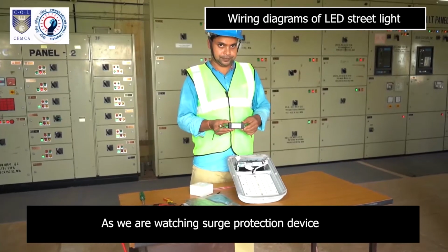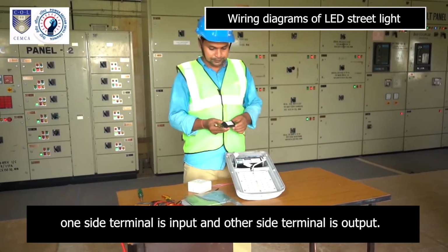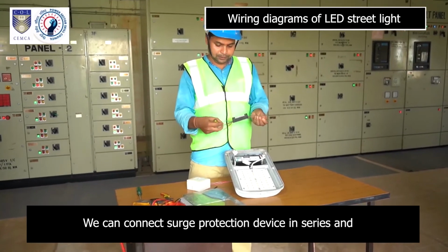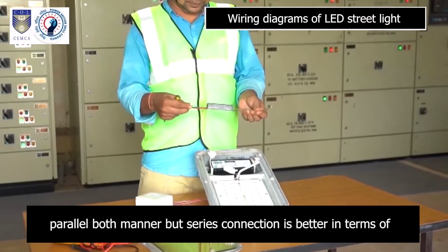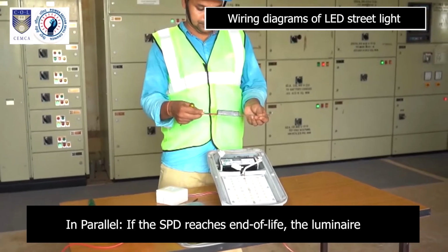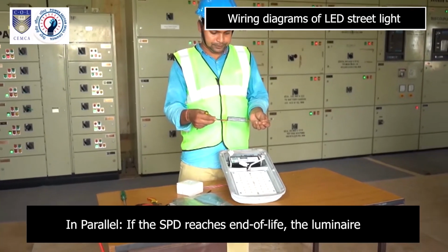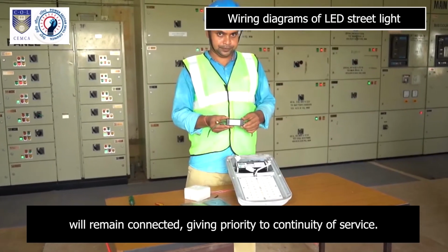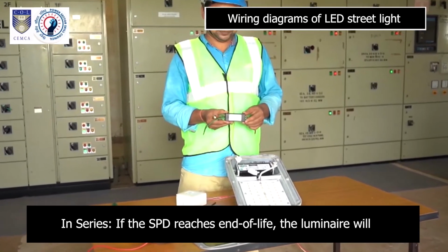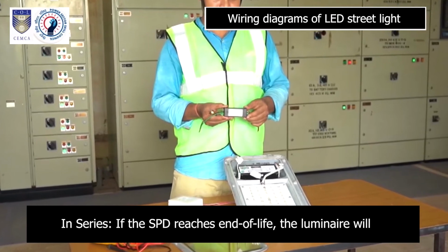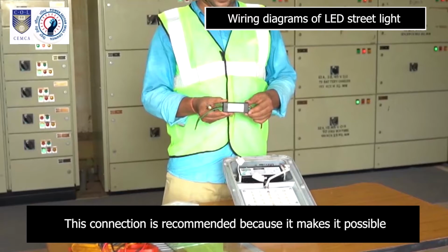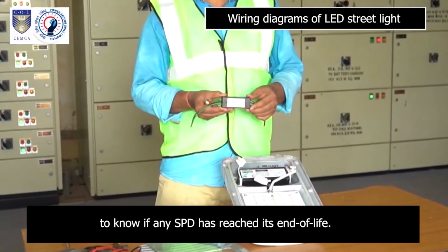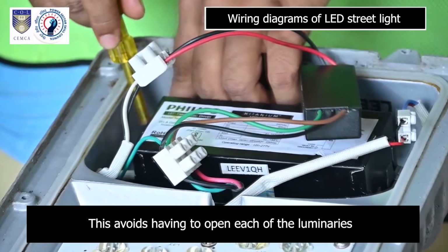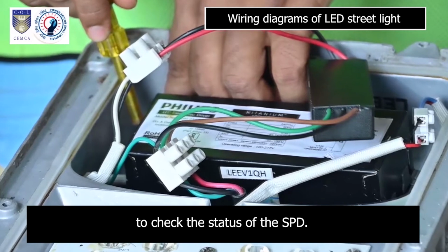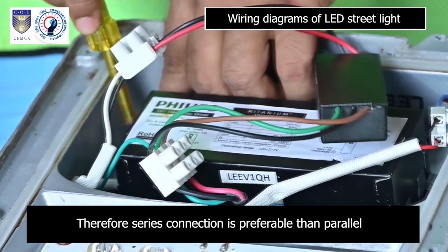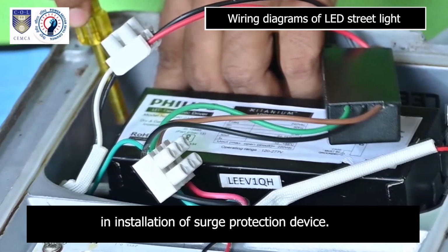As we are watching surge protection device, one side terminal is input and the other side terminal is output. We can connect surge protection device in series and parallel both manner, but series connection is better in terms of protection over parallel connection. In parallel, if the SPD reaches end of life, the luminaire will remain connected, giving priority to continuity of service. In series, if the SPD reaches end of life, the luminaire will be turned off, giving priority to protection. This connection is recommended because it makes it possible to know if any SPD has reached its end of life. This avoids having to open each of the luminaires to check the status of the SPD. Therefore, series connection is preferable than parallel in installation of surge protection device.